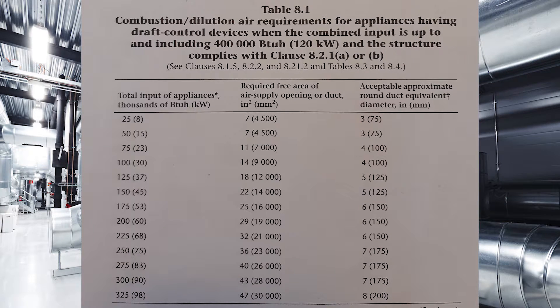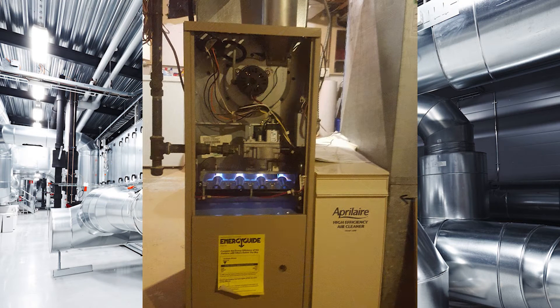We can see a difference between the last two examples. Table 8-1 gives us a larger air supply because it's also accounting for dilution air. But appliances without draft control devices don't use dilution air, so the fan-assisted appliances will have a slightly smaller air supply.